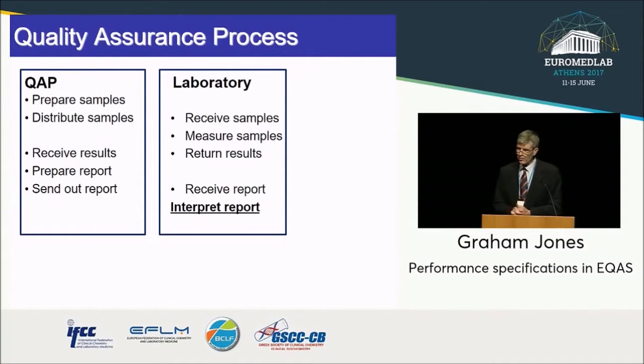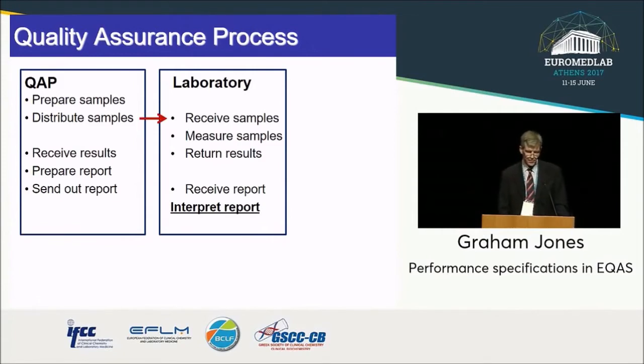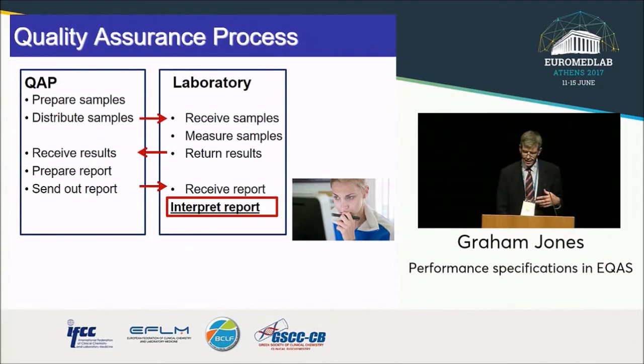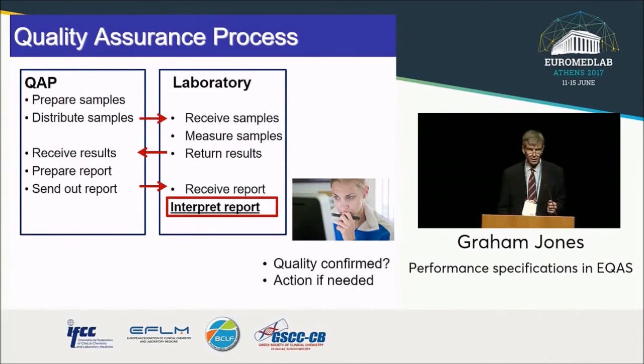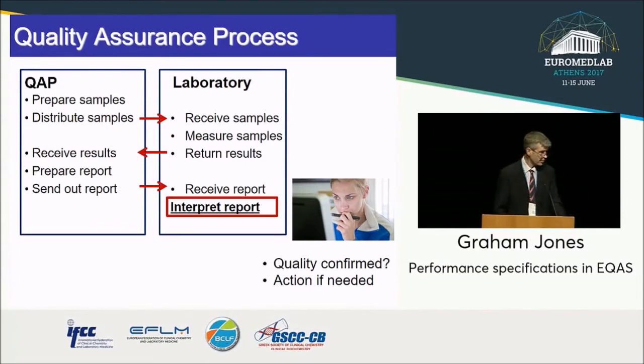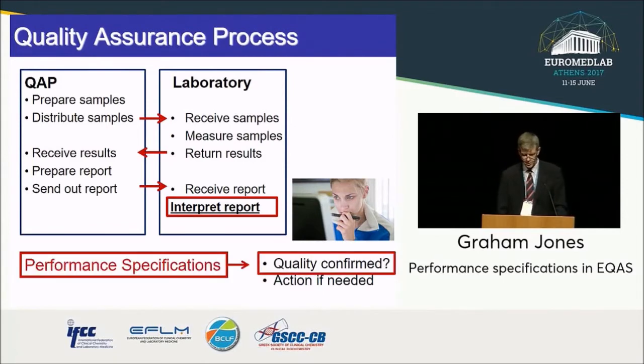Regarding the EQA process: there is usually a provider who prepares samples and distributes them to you. You receive them, measure them, and return the results. That provider then prepares a report that you receive and interpret. You might say, 'that's good, I've confirmed that my laboratory is working appropriately,' or you might say it's not performing correctly and you need to troubleshoot. How do we make that decision? Generally, we use the performance specifications provided by the external quality assurance program.